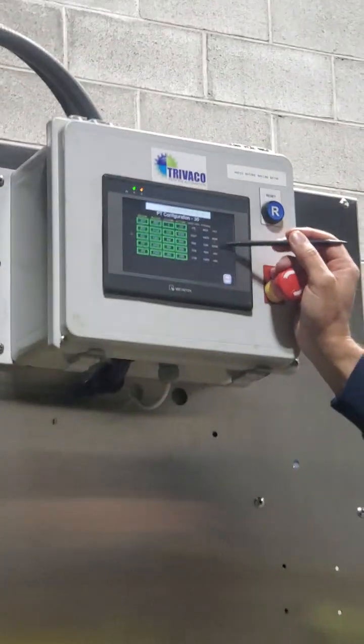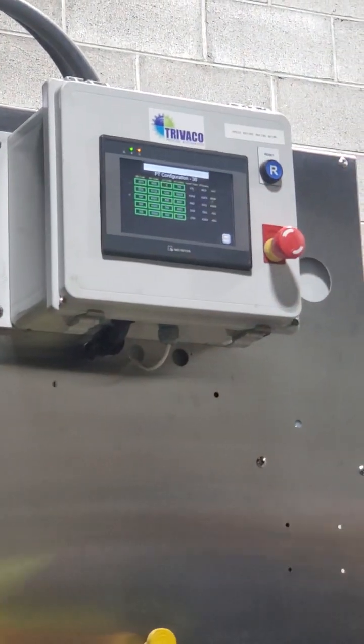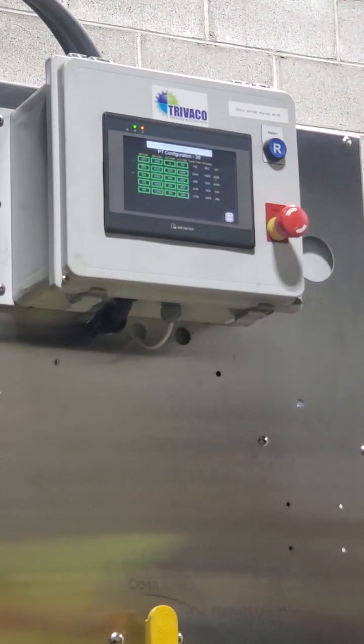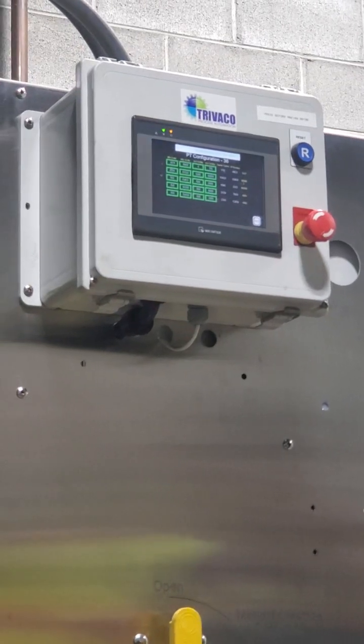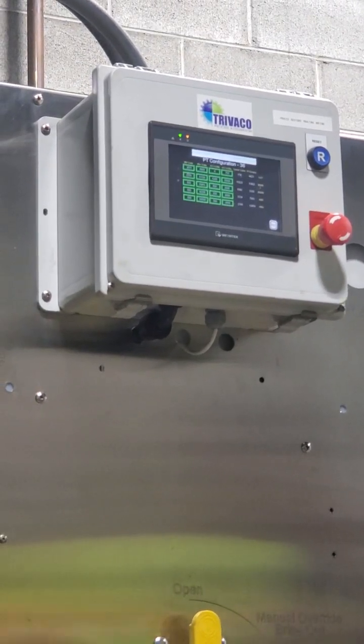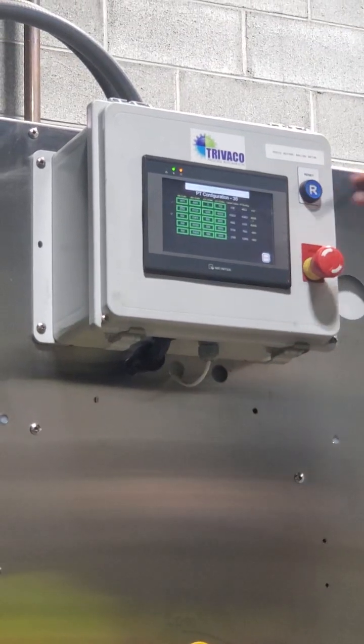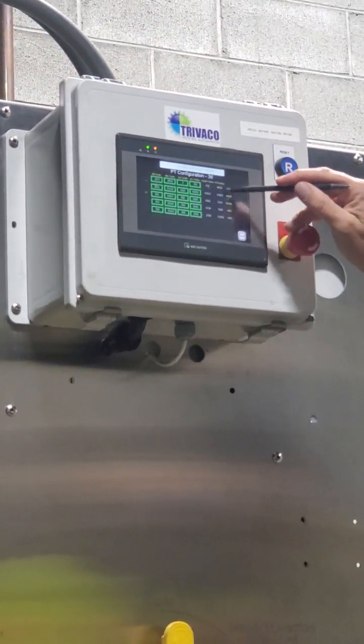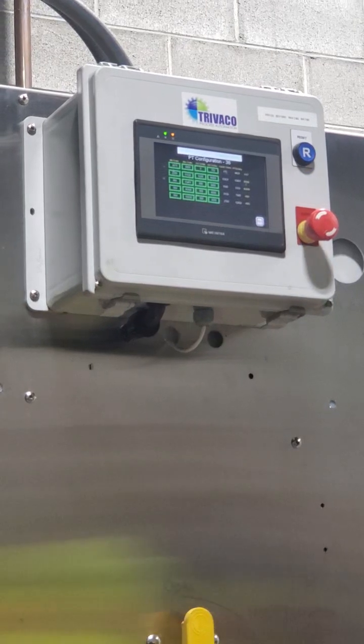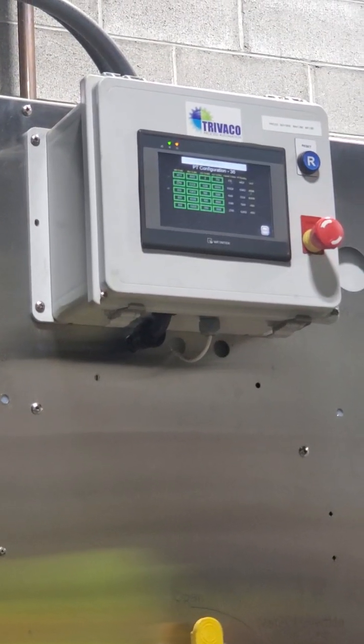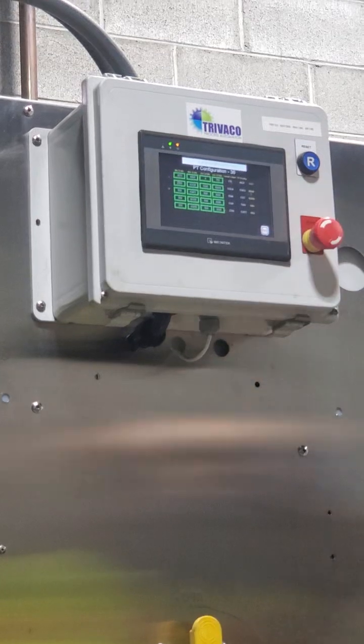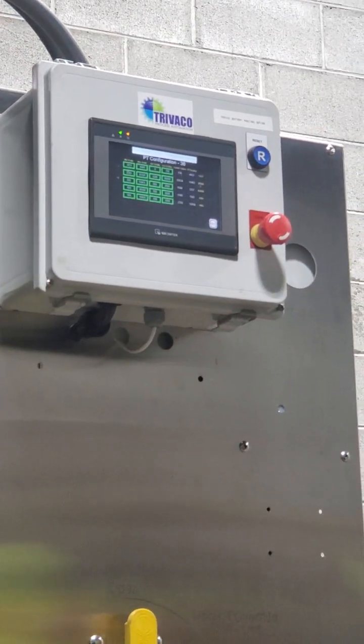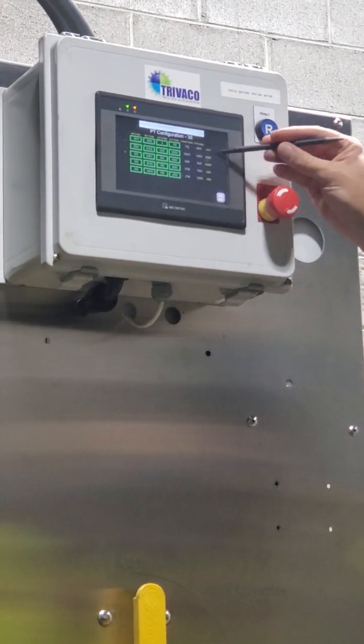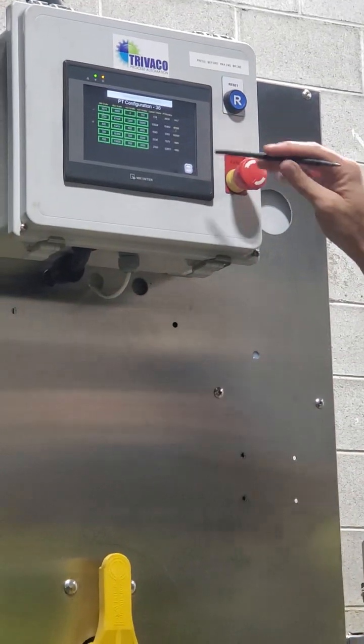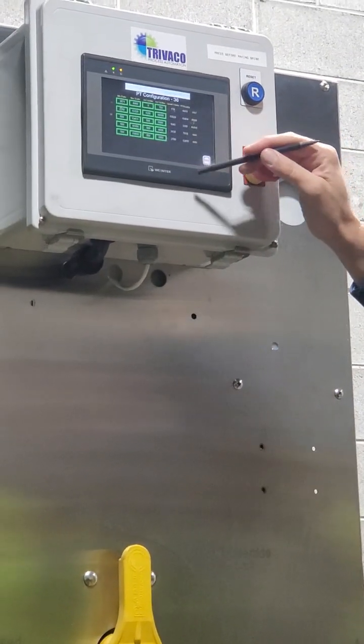Now let's say it has a leak. Like I said, those tubes are all pressurized. When you put in those pressure transducers, you tighten it down enough because there's an O-ring and it's sealed on top of that, and that creates a pressurized tube. So if those start leaking and it all runs out, these will read around 3900. Those are the two numbers to remember. 3200 is an electrical failure: you probably need a new transducer, and you need to check the wires. 3900 means there's some sort of leak in those tubes. And the same thing here, these will just go to 0.